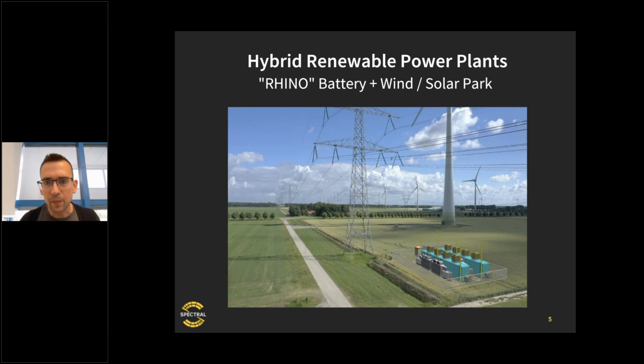In total, we'll have about 220 megawatts of wind and solar at this location, plus 36 megawatts of battery capacity, all connected behind the same high voltage connection to TenneT's transport grid. As with other sites, we'll be responsible for managing the peak power of the combined plant, because the grid connection is only rated to 180 MVA, while peak power can theoretically reach the range of 250. So we'll again be managing the power of the combined assets 24/7 once they're realized.